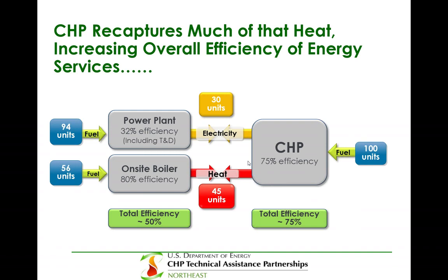In this instance, the CHP system will take in about 100 units of fuel and provide the same amount of energy as 150 units of input MMBTUs of energy as the traditional system. So in effect you're getting about a 50% increase. CHP, appropriately designed and appropriately sized - and we stress that, and we have tools to help with this, since this doesn't work everywhere - but where it does work, you can get marvelous system efficiencies, increasing by nearly 50% or more over the traditional method of purchasing your power directly from the utility and separately purchasing your thermal requirements.